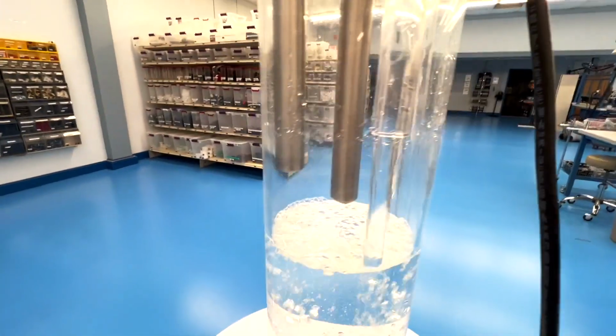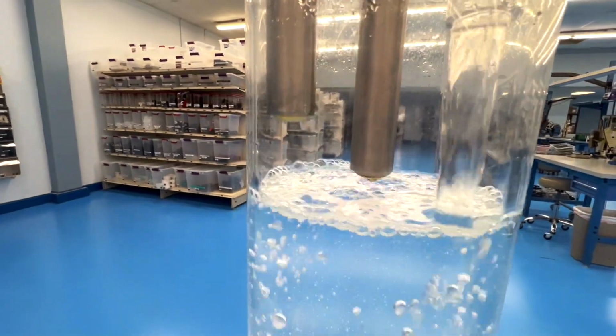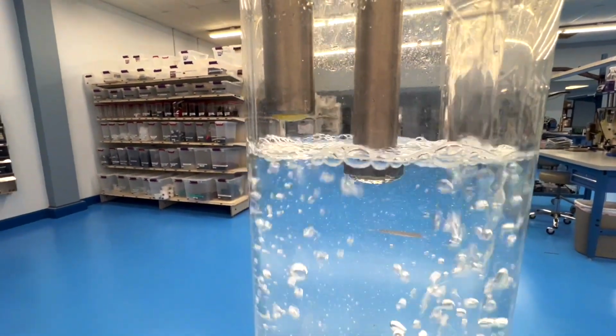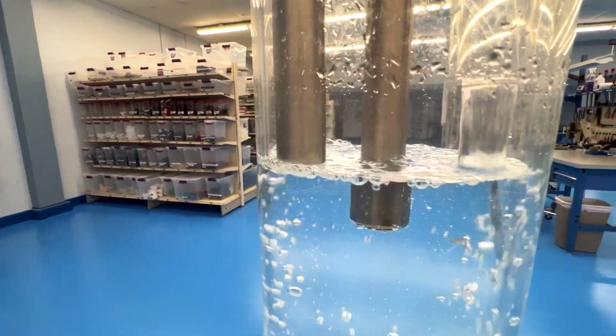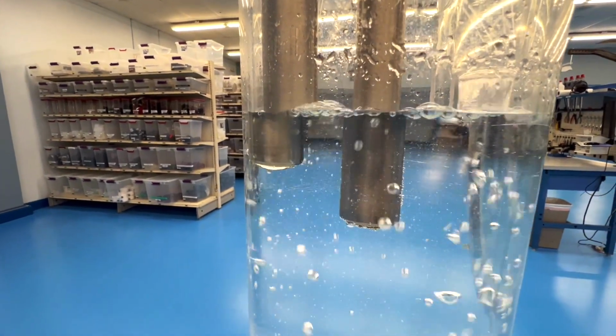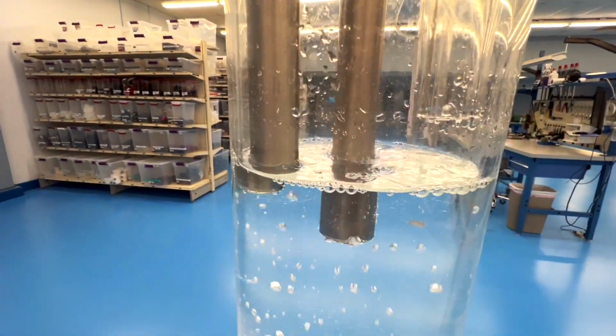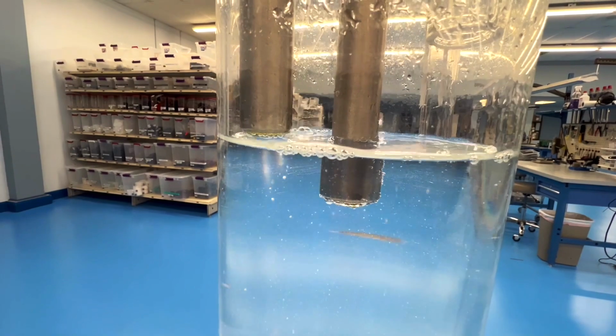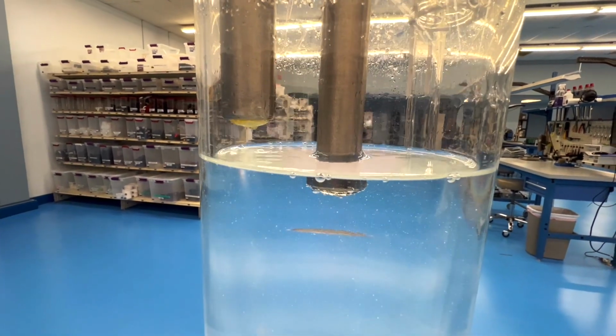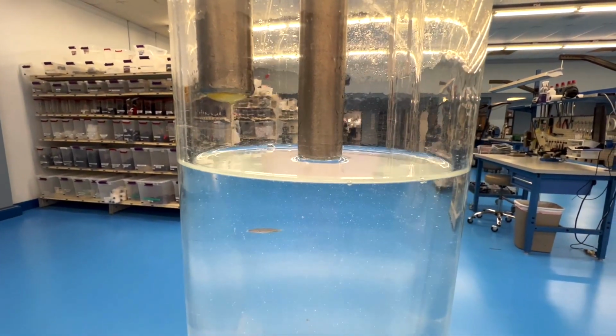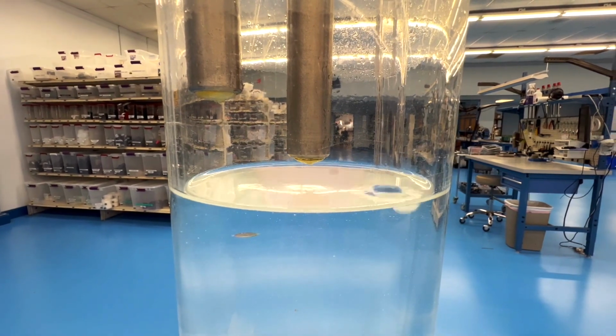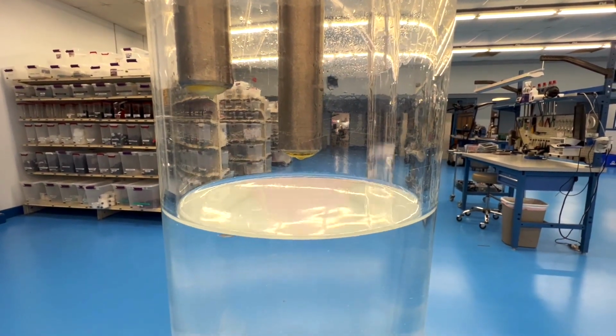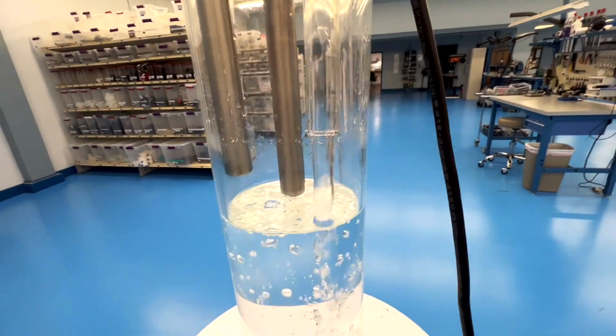We're almost getting to the bottom probe. Now the bottom probe has sensed the liquid level, but it's still low. Now the top probe has sensed the liquid level, and there's that 2-second delay I was talking about - that's why it goes a little bit above the top probe. Same thing on the bottom, it'll fall a little below. There, it stopped sensing liquid, but because of the 2-second delay it pumps up a little bit more.